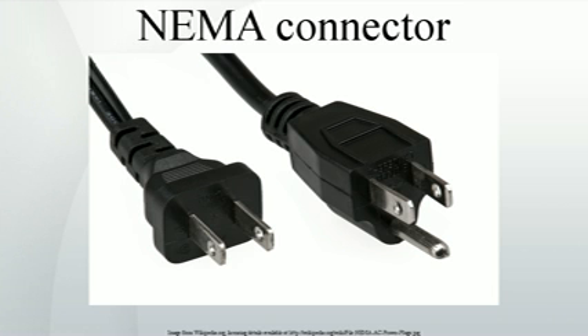Color code. The color of a device neither identifies its voltage class nor power system. Because the colors are not identified by national standards, the purpose of color coding a receptacle is set by the building owner. In this case, building owners may select brown, ivory, white, almond, gray, and black receptacles in the 5-15 configuration to blend with the decor of a room. However, although colors are not standardized by NEMA, some industries utilize colors for certain applications, following de facto standards.